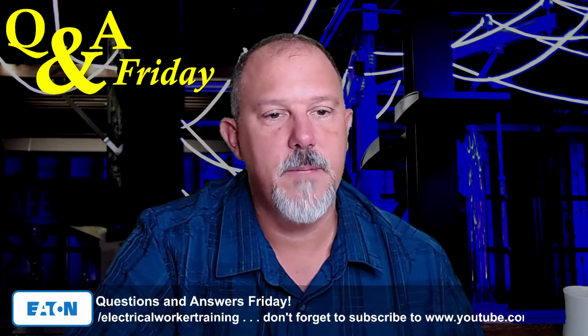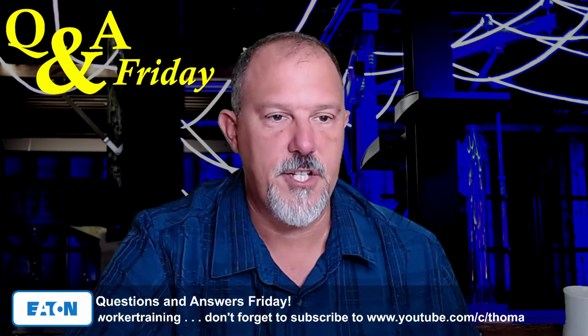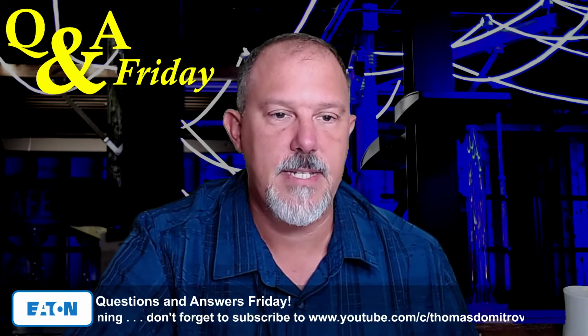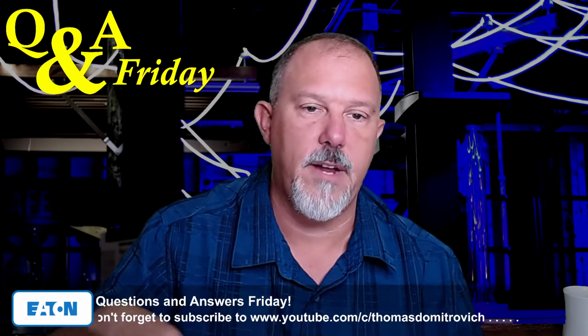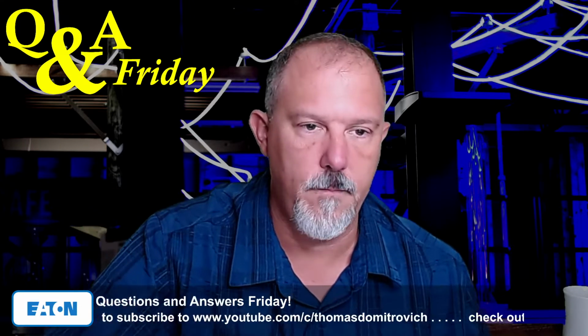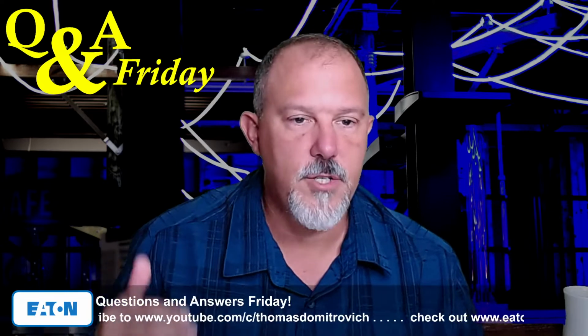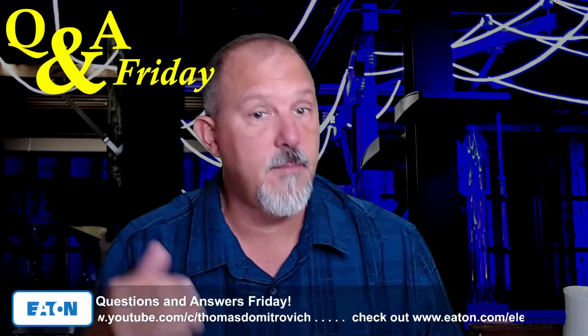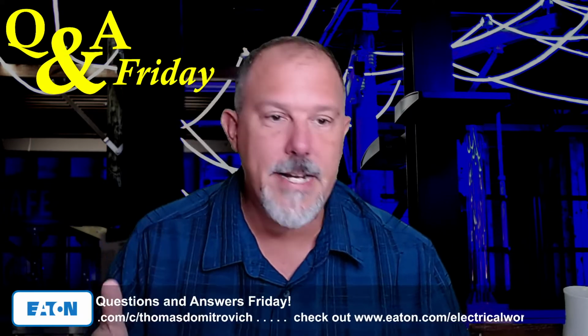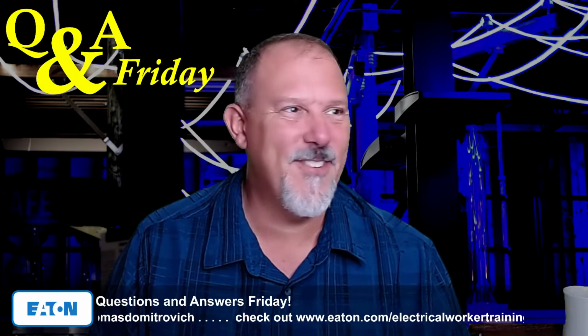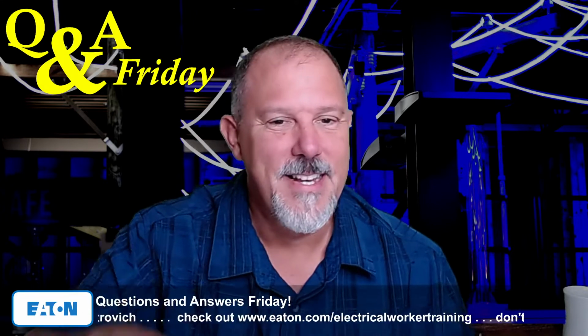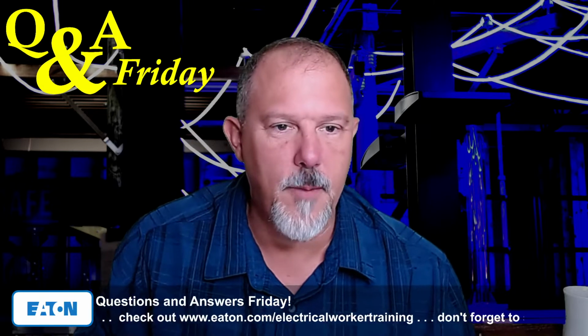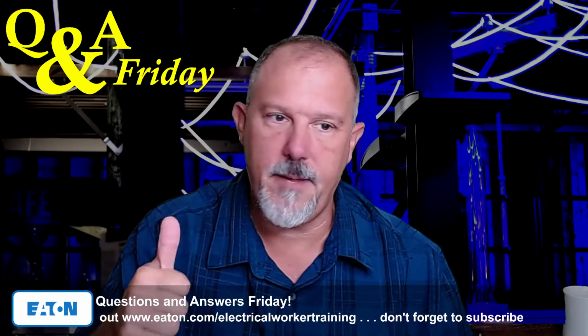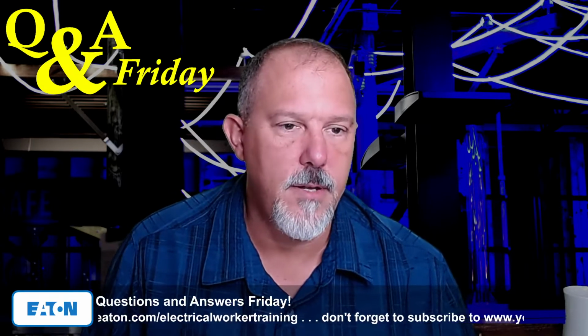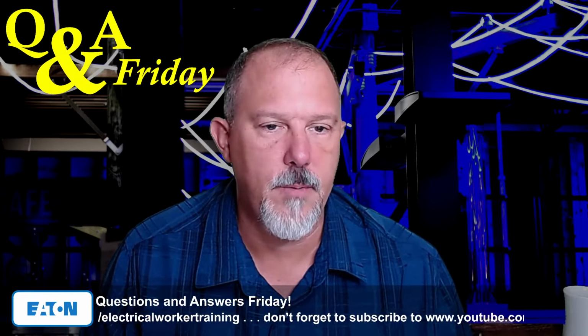The discussion was about energy codes and energy efficiency. The most energy efficient HVAC condensing units are VRF, or variable refrigerant flow systems. The compressor is driven by a VFD, or a variable frequency drive, or freak drive. I've never heard of a freak drive. Anyway, these systems have shown upwards of 50% savings in energy usage. Amen, brother. They have. Currently, most VFDs are not designed to operate with Class A GFCI.